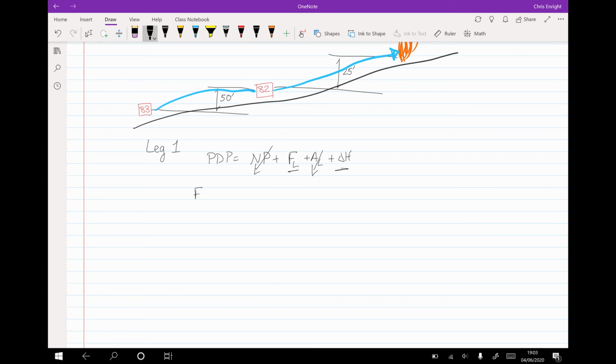So friction loss is going to be equal to, because it's 5-inch and we don't have a handy factor for it, we'll just do the math. C times Q over 100 squared times L over 100. FL equals 0.08 times, this was 300 GPM and 500 feet.